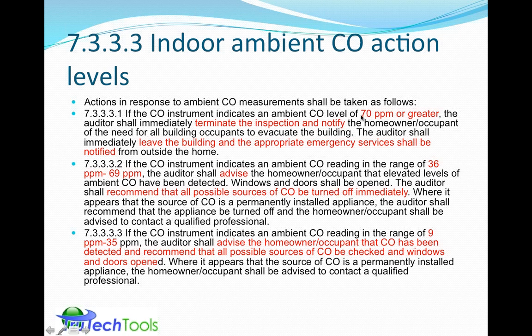But basically, at 70 parts per million or greater, you must terminate the inspection and notify the homeowners, leave the building, and notify emergency services. That's if you have more than 70 parts per million in the ambient level. The next section talks about the range of 36 to 69. You should advise the homeowner and recommend that CO possible sources be turned off immediately. And if that means it's a permanently installed appliance like a furnace or water heater, you must contact a qualified professional to do that shut off.